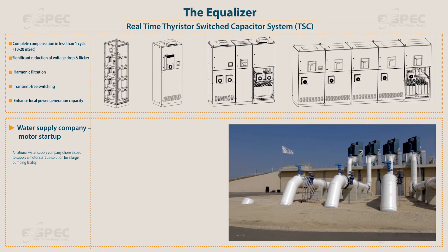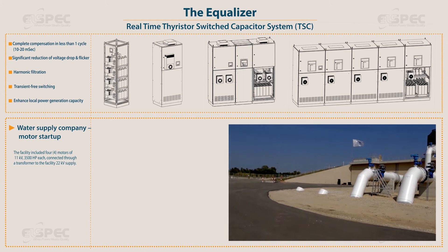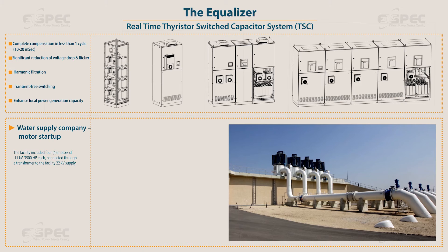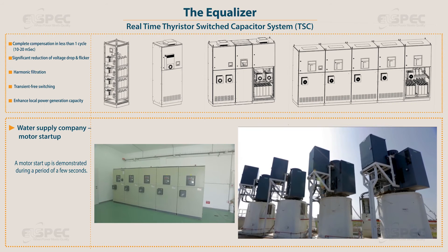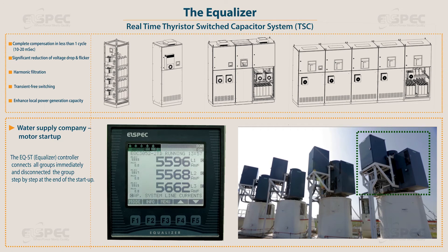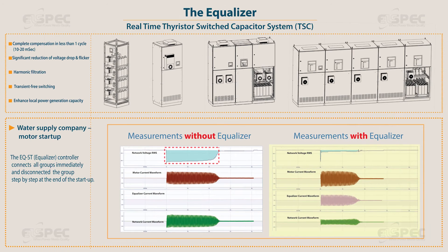A national water supply company chose Elspec to supply a motor startup solution for a large pumping facility. The facility included four motors of 11 kV, 3500 HP each, connected through a transformer to the facility's 22 kV supply. The EQ-ST equalizer controller connects all groups immediately and disconnects the groups step by step at the end of the startup.